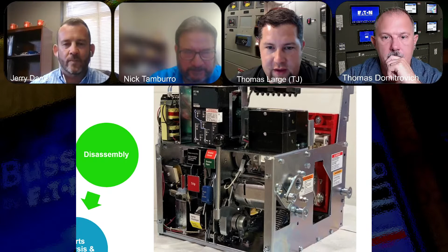Our reconditioning process takes it down to every nut, bolt, screw, and washer, taking that one breaker down to its few hundred different parts and pieces. Then cleaning, plating, replacement of hardware, complete reassembly and lubrication of the unit. It's a little different from remanufacturing, but a very in-depth process.